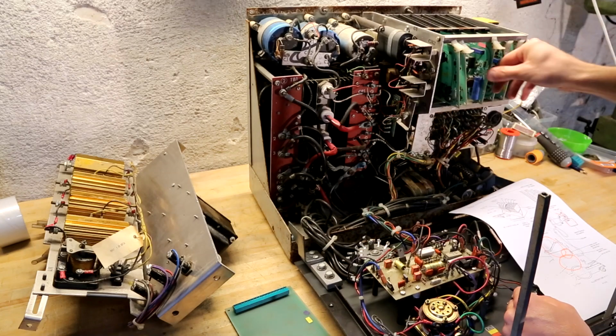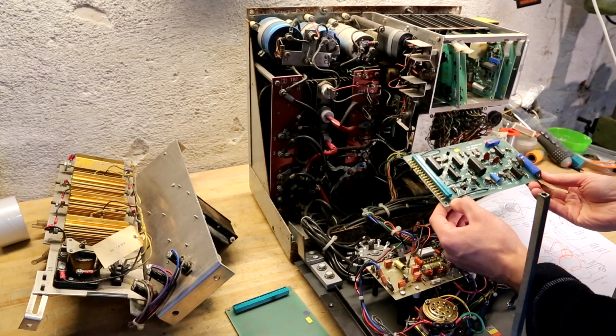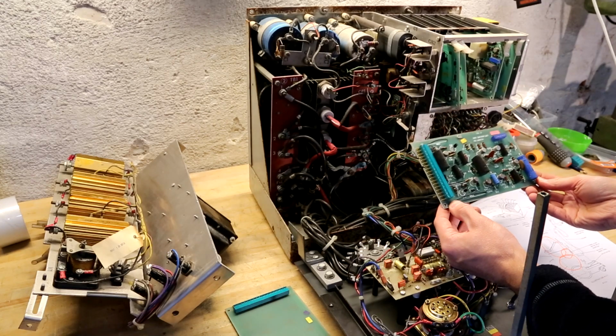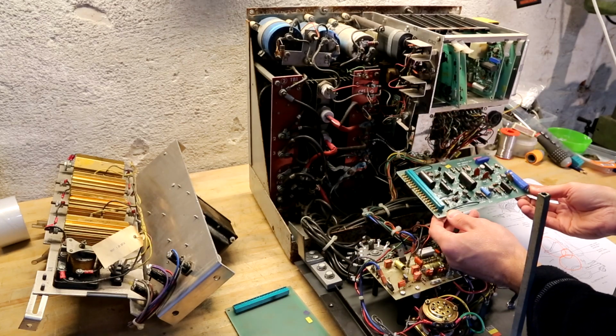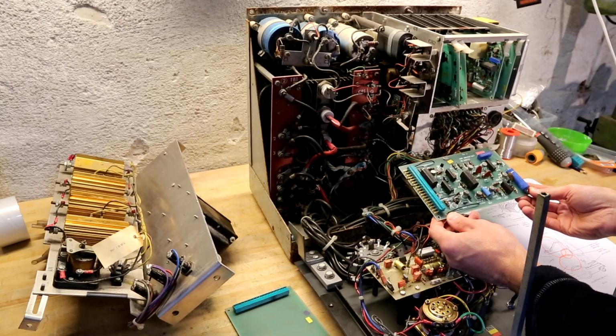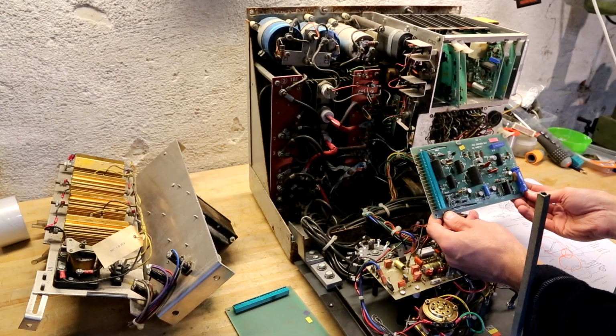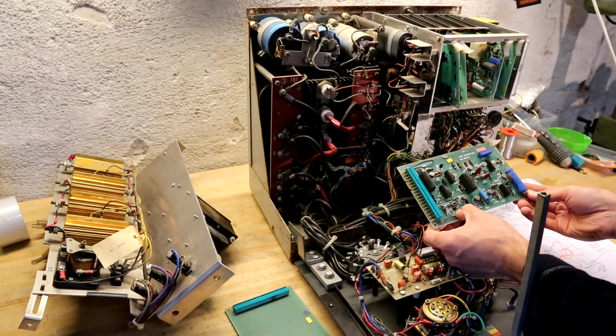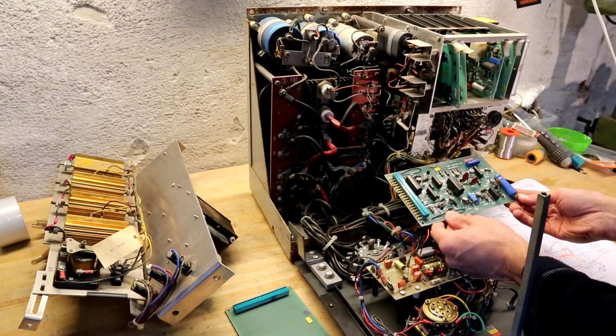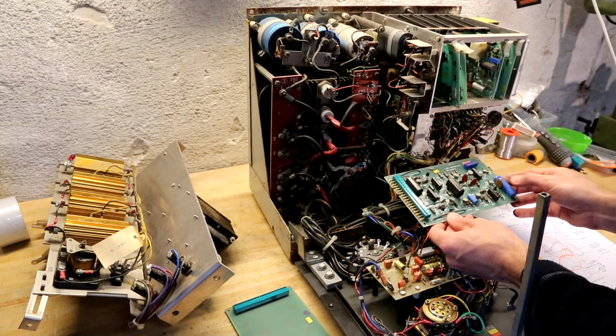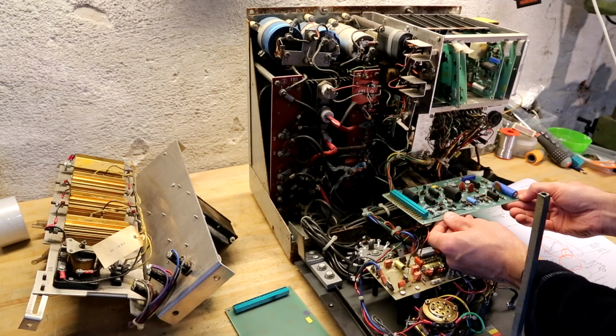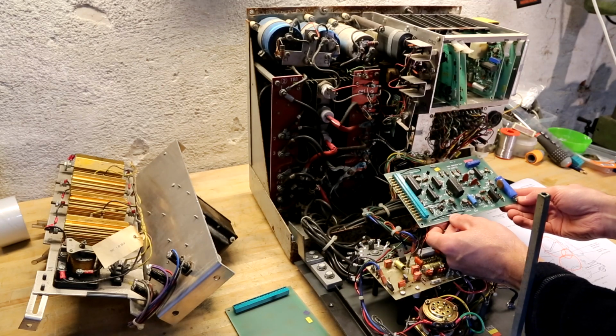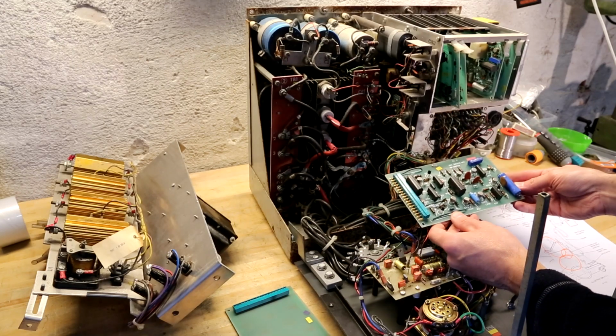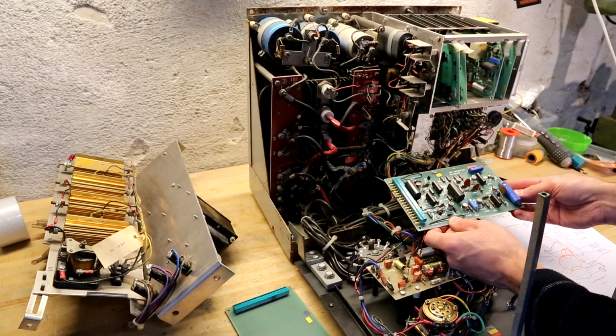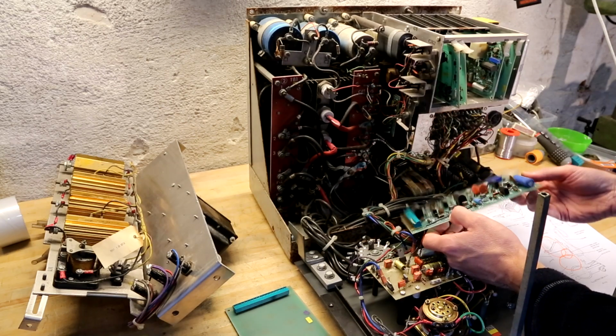Then card 3 says 500 Hertz inverter driver. This is the inverter driver for the main inverter, for the high voltage transformer, which is driven at 500 Hertz. Now this is probably inspired by the aviation industry, where you generally use 400 Hertz just to lessen the weight of transformers and the wiring and such. This was a mobile unit made at a time where mobility wasn't really that easy to make. So driving this at 500 Hertz makes sense to be able to build it smaller.